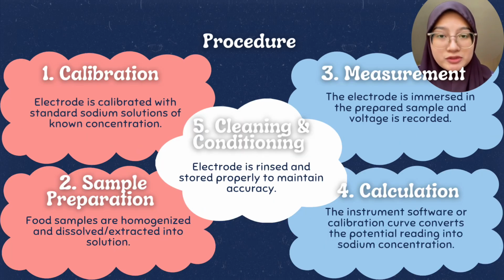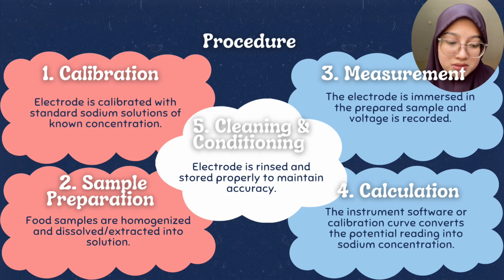So next, we're going to go to the procedure of ISE. Firstly, we need to calibrate. The electrode is calibrated with a standard sodium solution of known concentration. Secondly, sample preparation. Food samples are homogenized and dissolved or extracted into solution. Third, the measurement. The electrode is immersed into the prepared sample and the voltage is recorded. Fourth, calculation. The instrument software or calibration curve converts the potential reading into sodium concentration. And lastly, cleaning and conditioning. The electrode is rinsed and stored properly to maintain efficiency.